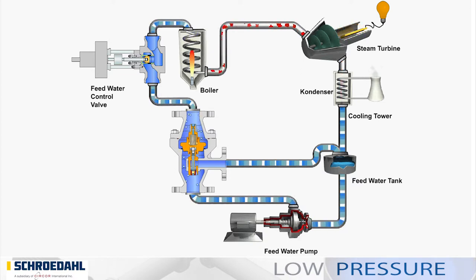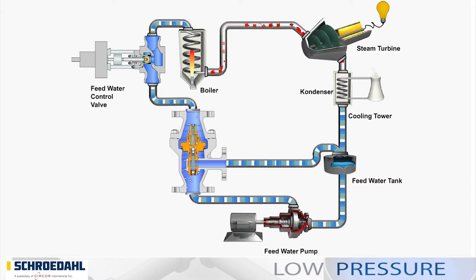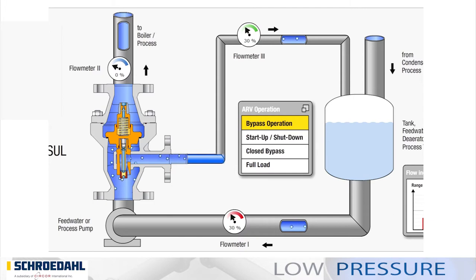How the automatic pump protection for centrifugal pumps works using our SUL valve as an example. The flow animation shows the bypass system circuit in a Schroedahl valve. The medium, which is mostly feed water but can also be individual process media, is fed to the pump. This conveys the medium through the Schroedahl fitting and a downstream valve to the turbine or to an alternative process. A bypass branches off from the Schroedahl fitting and connects the pump directly to the tank.